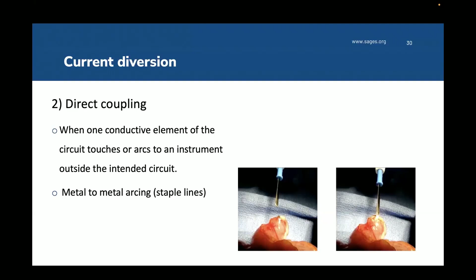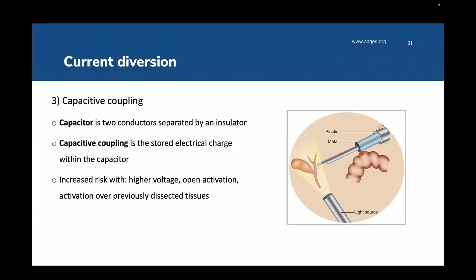Capacitive coupling. So what is a capacitor? It's basically when you have two conductors separated by an insulator, such as here, where these metal pieces are separated by a plastic insulator. Capacitive coupling is when you get a stored electrical charge within the capacitor. This becomes especially high risk when you perform what's called open activation. So, for example, your hook is not touching any tissue, there's nowhere for the current to go, but you're activating the instrument. This can lead to electromagnetic charge getting stored within the capacitor itself. And then you could touch other tissue. It could also happen outside of the view of your camera and lead to injury.